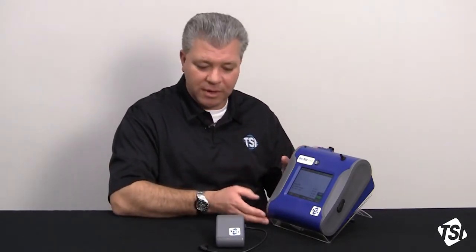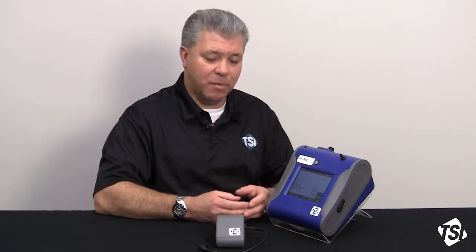Two of those that come to mind readily are indoor air quality monitoring, where you may be monitoring for 24 hours at a time, or fugitive emissions monitoring, a very common outdoor environmental monitoring application that the DustTrak is widely utilized for. In the environmental application, the DustTrak would be put into an environmental enclosure. For the purpose of this video, I'm not going to utilize an enclosure, but I'm simply going to show you how to attach and set up the Auto Zero module for a sample run.